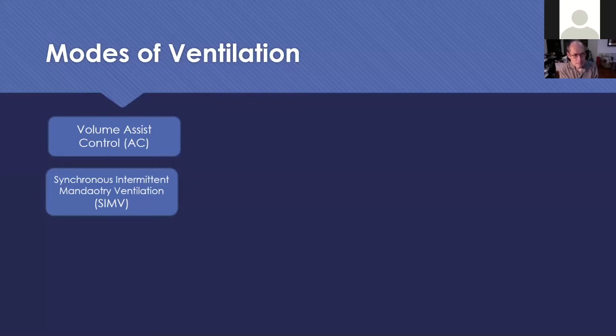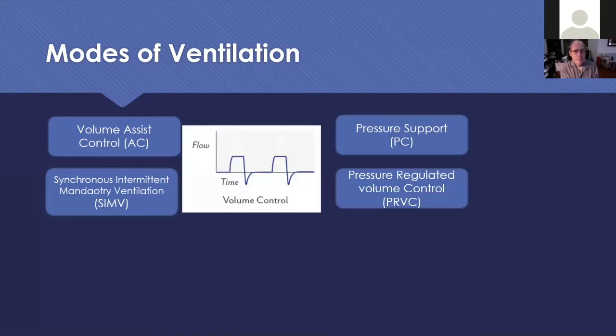So it's compliance dependent. If the compliance goes low and the patient has an increase in his pressure, the system will give you an alarm. In contrast to the pressure support or the pressure control system, which basically guarantees a pressure per unit of time. Here, the flow is not the same in every cycle. It's compliance dependent. So if the patient has good compliance, it will give the desired volume. If the patient's compliance is low, the volume is going to go low according to the patient's pressure.